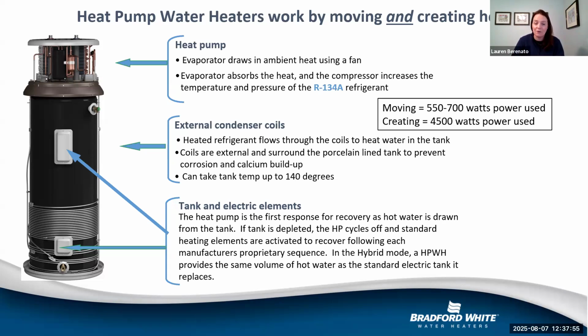But I agree, because you're looking at this and you're like, well, I can set my heater lower. Is that safe? Is that not safe? So it's really weighing the risk factors. If you are the engineer signing off on the drawing, I would not put it in vacation mode. You do not want to be open to litigation possibly because of the recommendation you give.